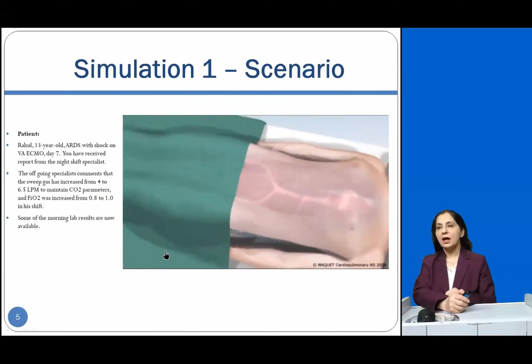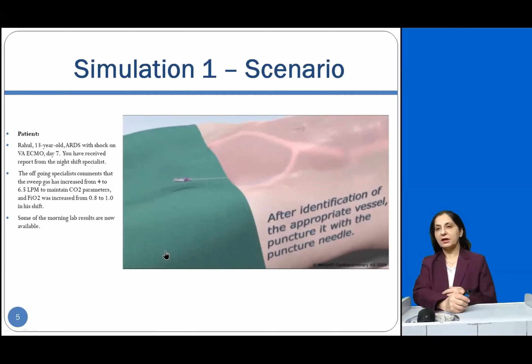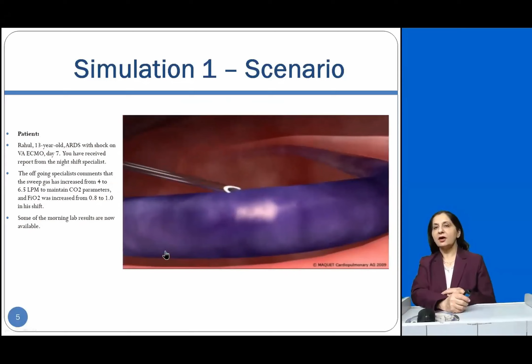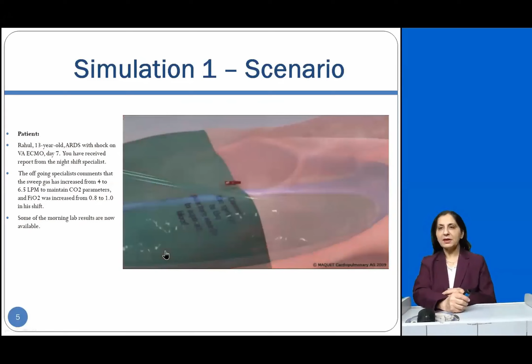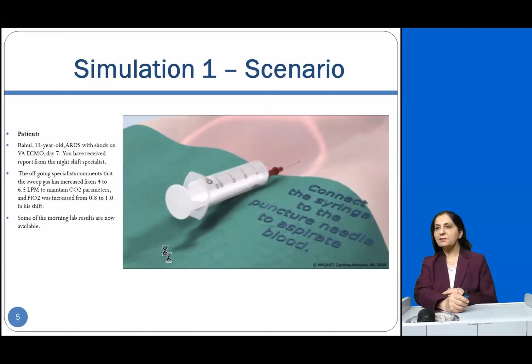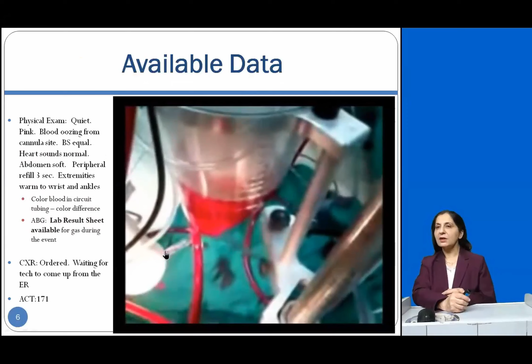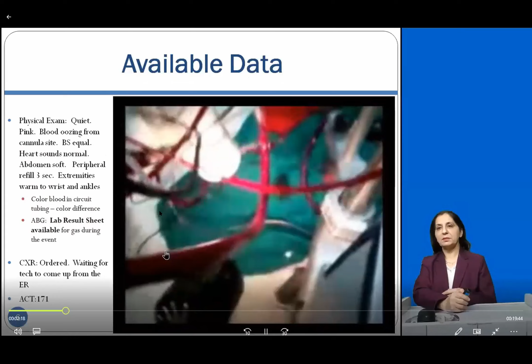on VA ECMO on day 7, you receive a note that suddenly there's a need to increase the FiO2 from 0.8 to 1 and increase the sweep gas from 4 to 6.5 liters per minute. And the patient, otherwise stable with the saturation, CVP and all remaining the same as baseline, is suddenly having seizures. When you receive a note like this, you start looking at the circuit, the venous reservoir, the oxygenator. If you're on a roller pump or a centrifugal pump, it would be very, very different.